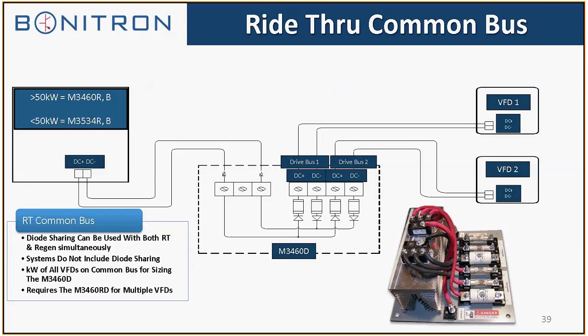When talking about ride-through common bus, the M3460D units are required to tie the inverters together at the DC bus. They're going to be specified for the number of drives or number of drive connections required, determined by the amount of inverters that you're going to be tying together.